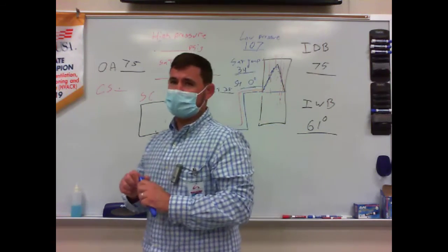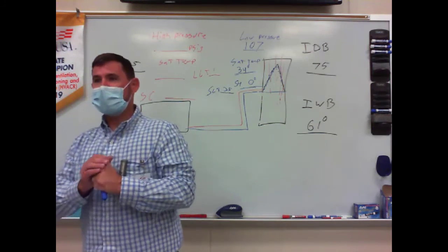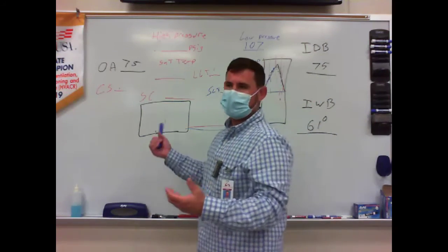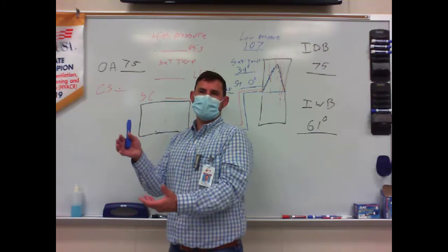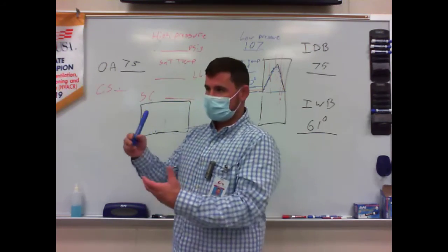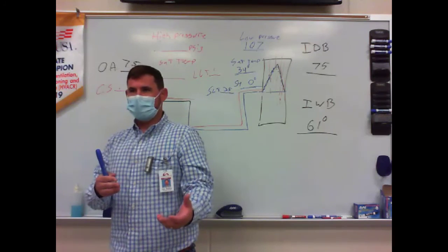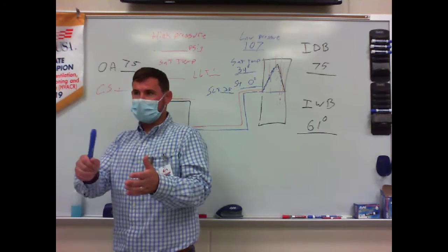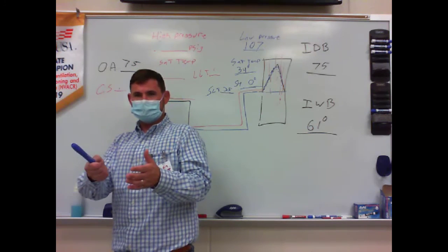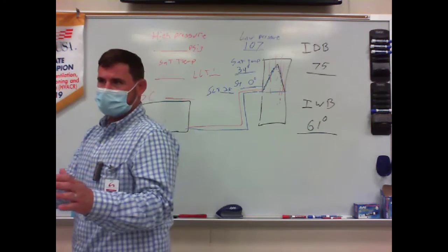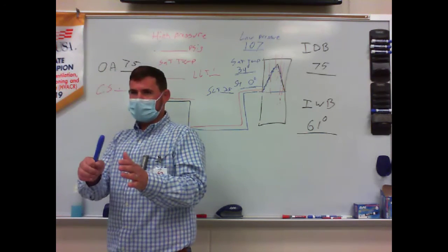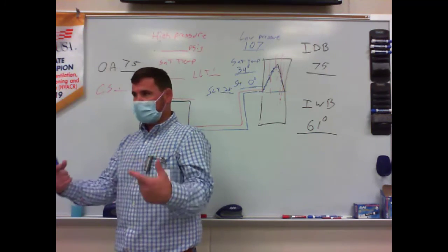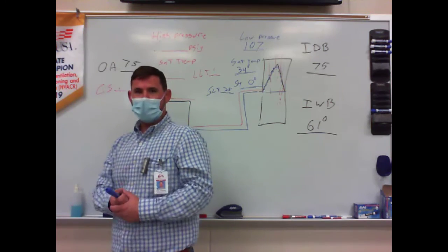We can damage our compressor by weighing it into the low side, but I have to weigh it into the low side because the high side pressure is too high. The pressure on that high side is higher than the pressure in that tank of refrigerant, so it won't go into the system. The only way to get it in the system is to suck it in through that low side, right? But we're sucking liquid refrigerant in, so we don't want to slug our compressor, so we slowly throttle it in a little bit at a time. So don't damage my compressors. Slowly throttle it in. Once you've put some in, we wait another 5 or 10 minutes and let the system stabilize, do all our checks again, and see if we need to add more.